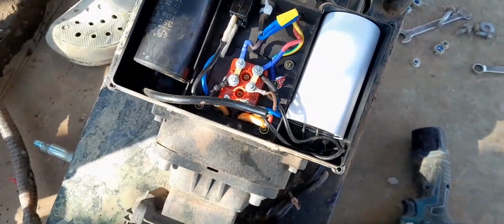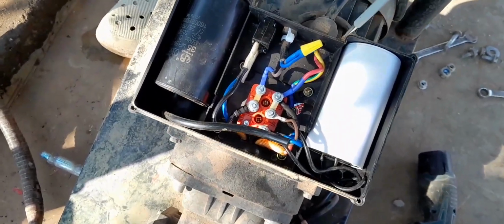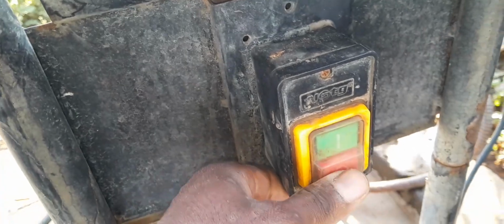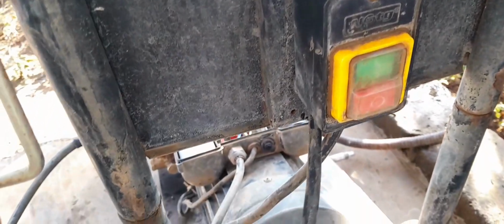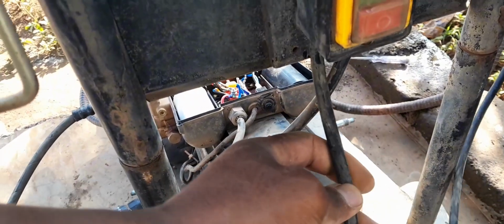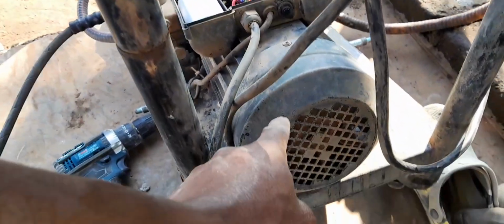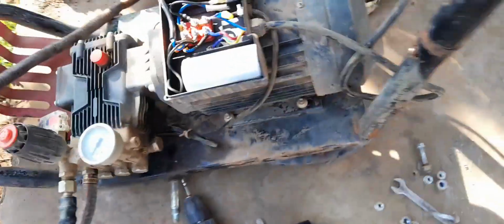So the next step, I checked to see whether our current is working the way it's supposed to be. We started with this start and stop switch here. Basically, when you start your switch, the current that is coming from our supply here should be reflected on the supply that is feeding the motor. I checked whether the live and neutral terminals are working correctly, and they were also working correctly.